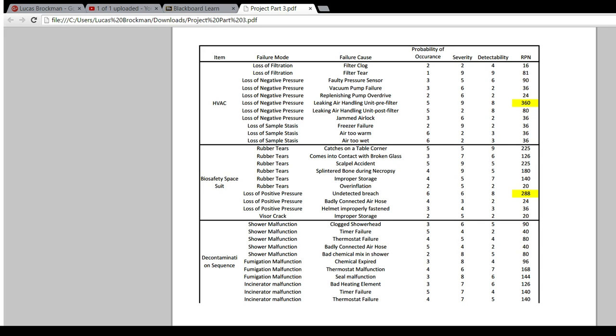Looking forward at the decontamination sequence, here is where I put fumigation malfunction. Some samples that are passed out are sterilized with a chemical fumigation process, and while this is very effective, it happens mostly in a closed room that isn't often watched over. So if anything were to go wrong, detectability before it becomes catastrophic is low, and it could be very catastrophic as those samples go out into the main building.